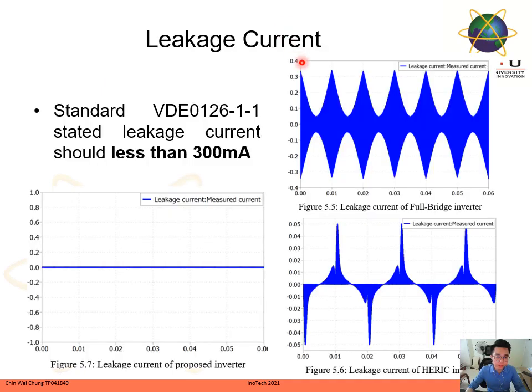As stated in the problem statement, the leakage current in transformerless inverter can cause electric shock and electromagnetic interference. The standard VDE 0126-1-1 states that the leakage current must be kept below 300 mA. This slide shows the simulated leakage current of the conventional full-bridge transformerless inverter, which has a peak current of 340 mA. The HERIC inverter, which is based on zero-state decoupling topology, has a 50 mA peak current, while the leakage current for the proposed transformerless inverter, which is based on common ground topology, is constantly zero. This shows that the proposed inverter is capable of eliminating the leakage current.